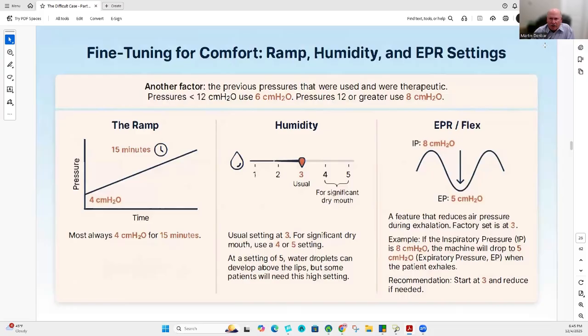What the EPR is, expiratory pressure release, I believe the EPR is on the ResMed machines and the Flex is on the Respironics machines. They're the same thing. The factory setting is 3. So what that means is if your inspiratory pressure is at 8, the machine will automatically drop to 5, so it's easier to exhale, just for comfort. If the EPR is set at 2 and the initial inspiratory is at 8, the expiratory is going to be 6. If it's 1, it'll be 7. And if it's 0, you'll inspire at 8 and the expiratory is going to be 8.